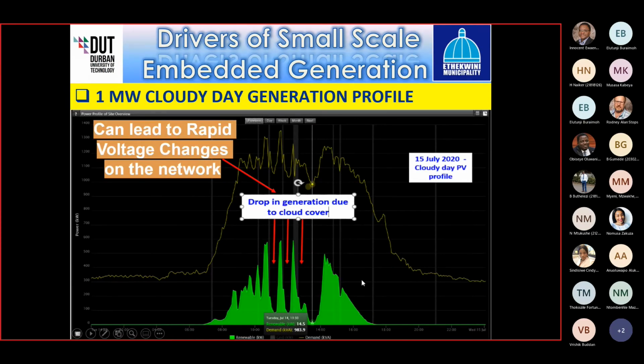So there's another example from another PV system where you have sudden cloud cover. And what this does is it results in quite a substantial reduction in production. And it does not give you a nice bell curve. So it gives you this jagged edge curve, which obviously from a network operator point of view, you don't really want that, because what it can do is lead to what we call rapid voltage changes in the network. It's typically similar to losing generation, dropping off and coming back, and then the grid taking over. So it starts to change the network voltages. And depending on how frequently it happens, it could cause substantial problems on the network.